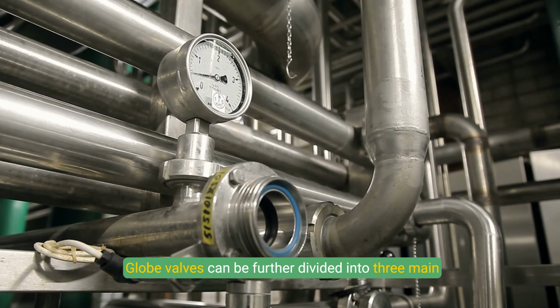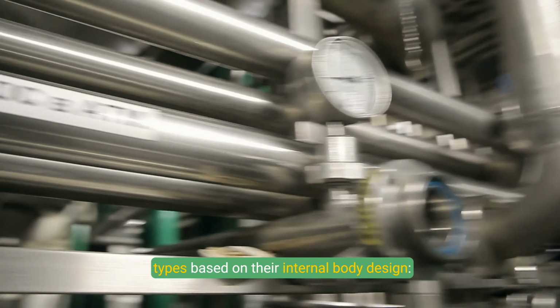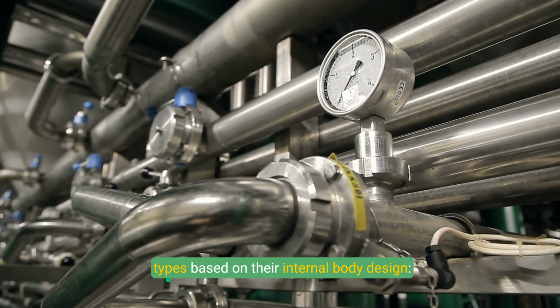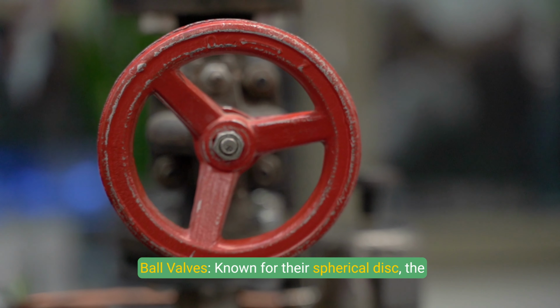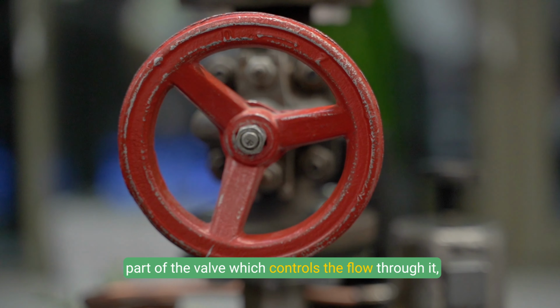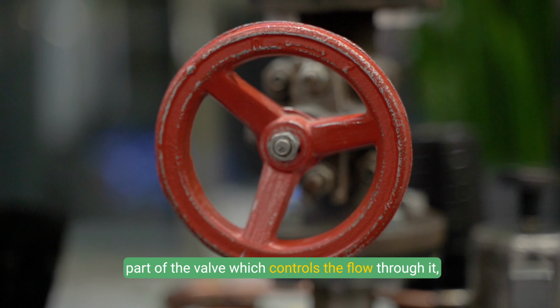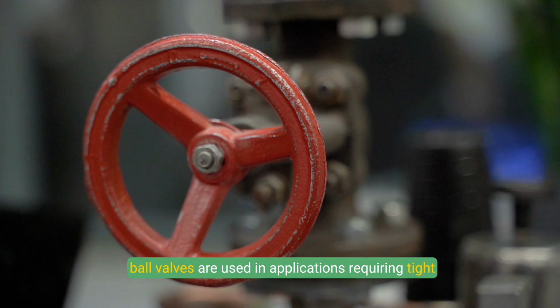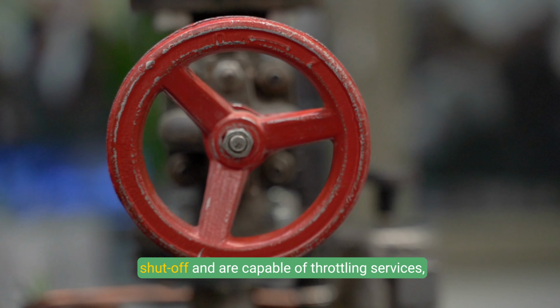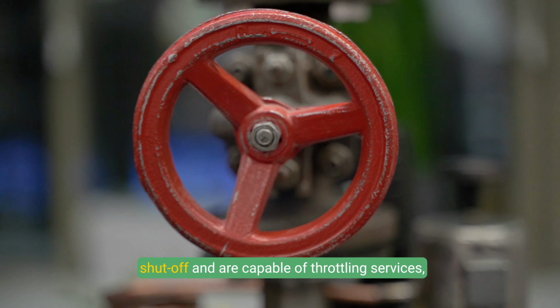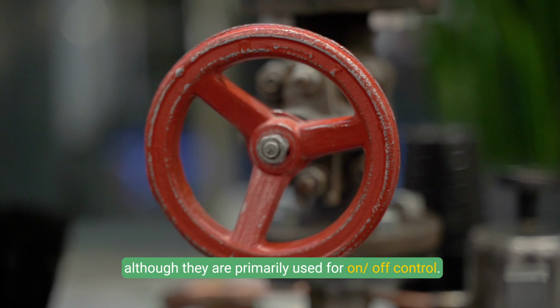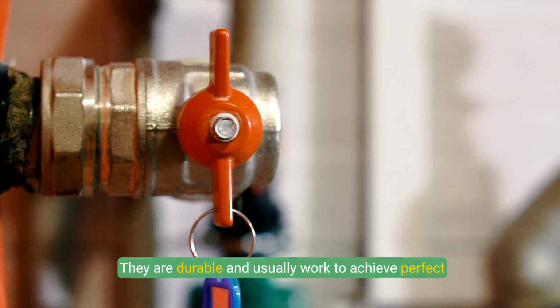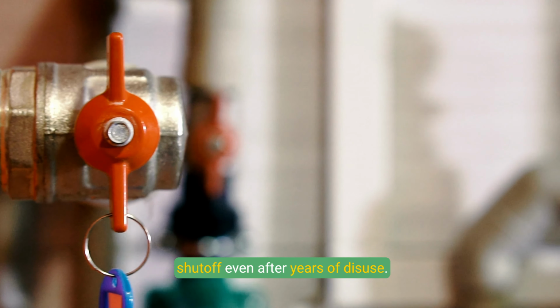Globe valves can be further divided into three main types based on their internal body design: T-pattern, angle pattern, and Y-pattern. Ball valves. Known for their spherical disc, the part of the valve which controls the flow through it, ball valves are used in applications requiring tight shutoff and are capable of throttling services, although they are primarily used for on-off control. They are durable and usually work to achieve perfect shutoff even after years of disuse.